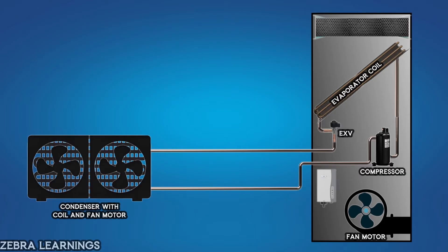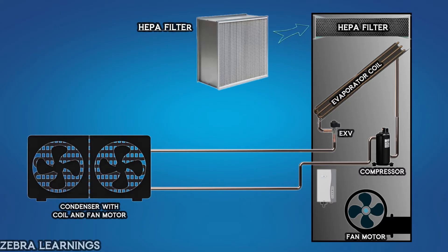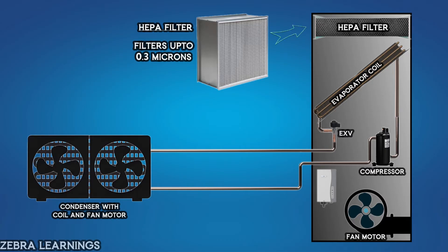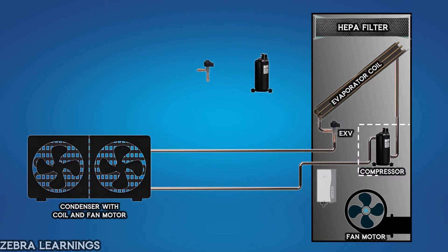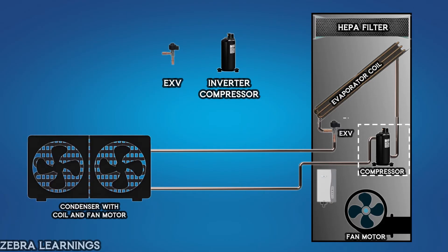In PACs, high-quality filters like HEPA filters are used. These filters can trap particles as small as 0.3 microns in size, ensuring that high-quality air is supplied to the data center. The use of an inverter compressor and electronic expansion valve allows for very precise control of the room temperature.